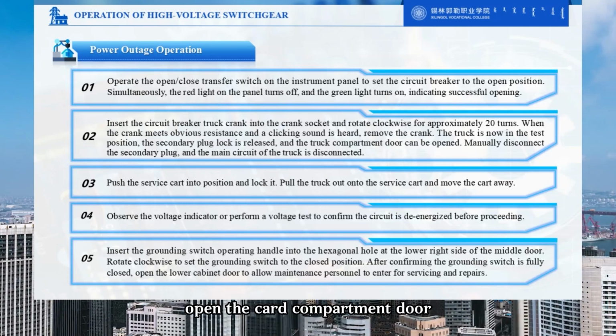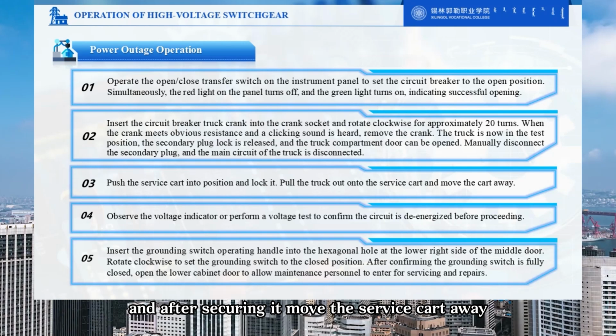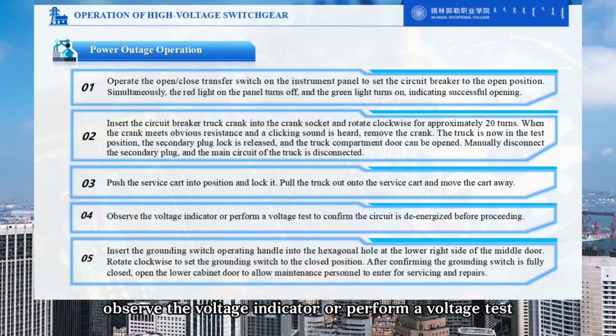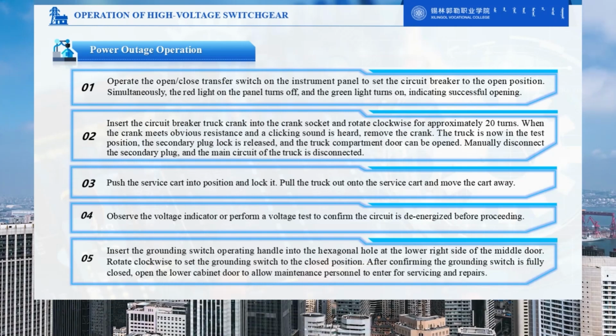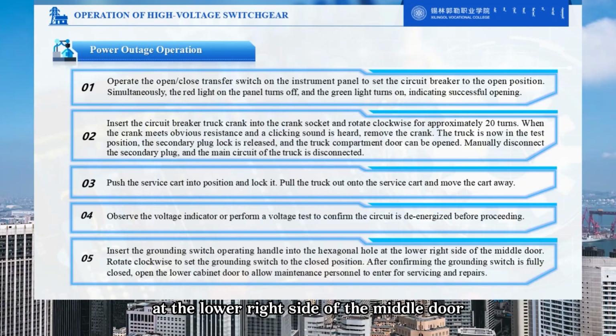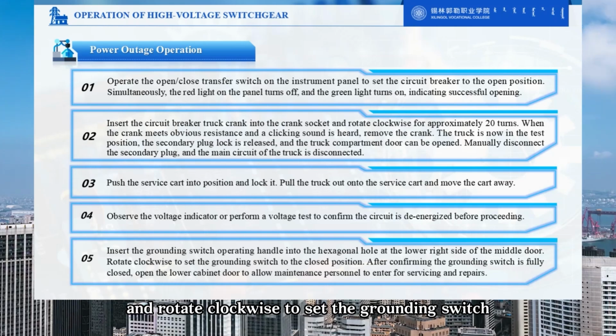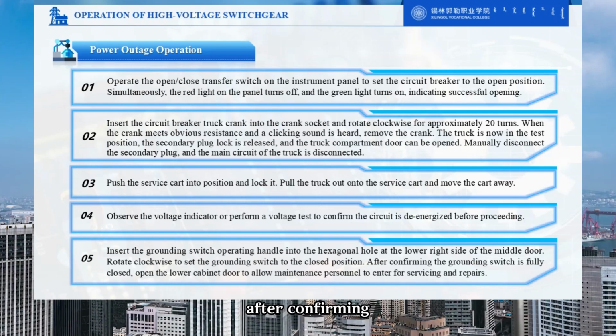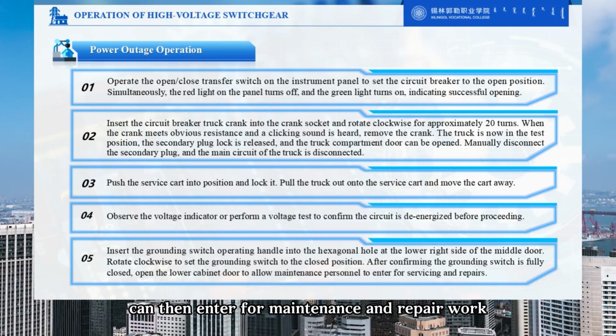Open the truck compartment door and manually disconnect the secondary plug. The main circuit of the truck is disconnected. Push the service cart into position and lock it. Pull the truck out onto the service cart, and after securing it, move the service cart away. Observe the voltage indicator or perform a voltage test. If no voltage is present, you can proceed with the operation. Insert the grounding switch operating handle into the hexagonal hole at the lower right side of the middle door and rotate clockwise to set the grounding switch to the closed position. After confirming that the grounding switch is indeed closed, open the lower door of the switchgear. Maintenance personnel can then enter for maintenance and repair work.